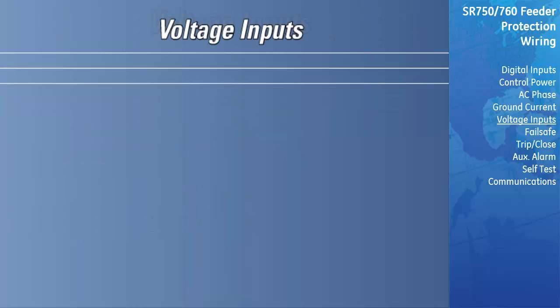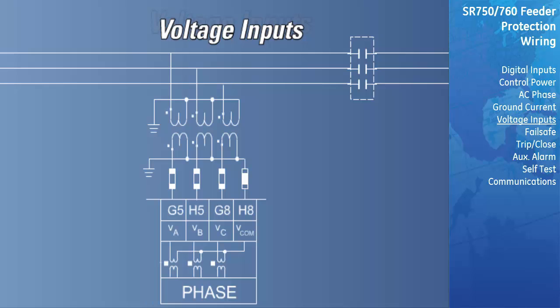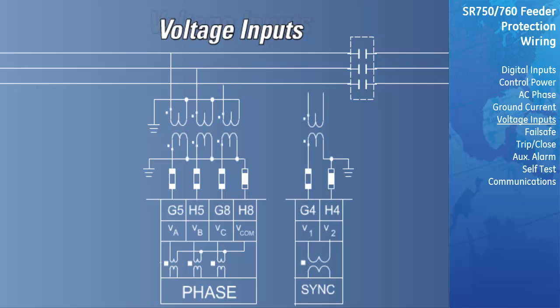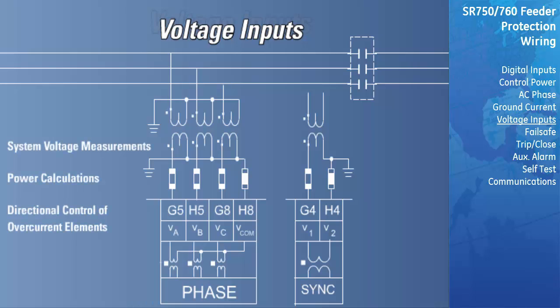There are a total of 4 VT inputs available with this relay. They are the 3 bus VTs along with the line VT. The bus VTs are used for measuring the voltage in the system. Power calculations, voltage protection, and frequency protection are all based on these metered values. The bus voltages are also used for the polarization of the directional overcurrent elements.